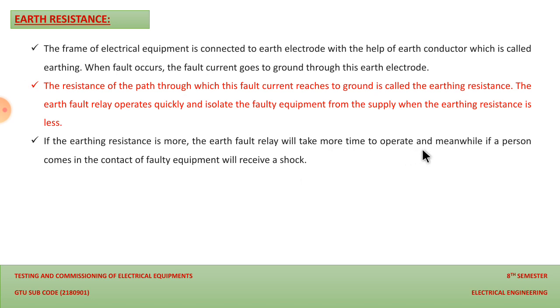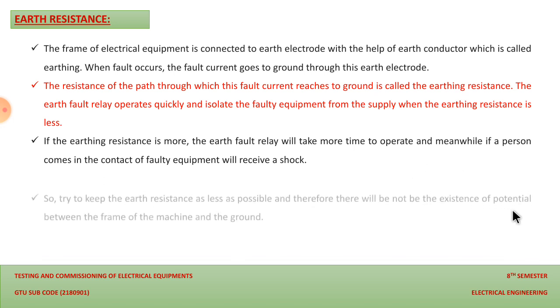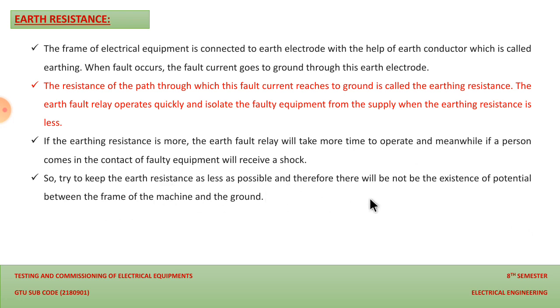We should keep earth resistance as low as possible, so we can operate the earth fault relay in minimum time, and so that we can remove the faulty equipment from the electrical supply, and we can protect the instrument as well as the human being who comes into contact with the electric shock. So try to keep the earth resistance as low as possible, as we have already discussed, and therefore there will not be the existence of potential between the frame of the machine and the ground. So no potential is created, and that's why no current is transferred through the human body which comes in contact with that equipment.